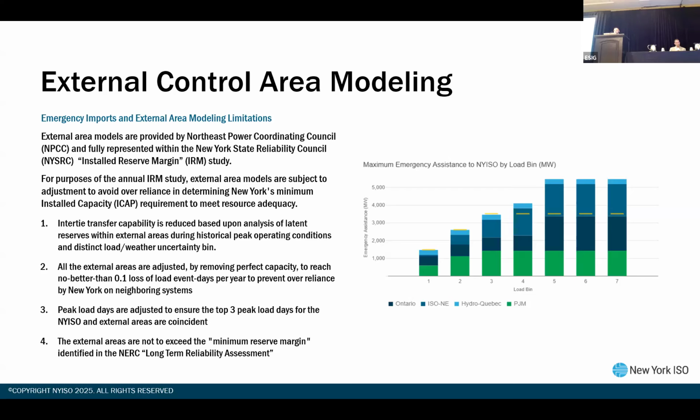So our result after improving our emergency assistance limits here was actually an increase in the margin of 700 some megawatts. So that really tells you that when you start to dial down these emergency limits and take a less optimistic view and try to characterize your system as more coincident in terms of when they're seeing constraints, you actually need another 700 megawatts of local supply to help meet those same reliability needs. So that tells us that we were certainly getting a lot of benefit, but it's not clear that we were able to withstand these if we actually got into those situations and operations.